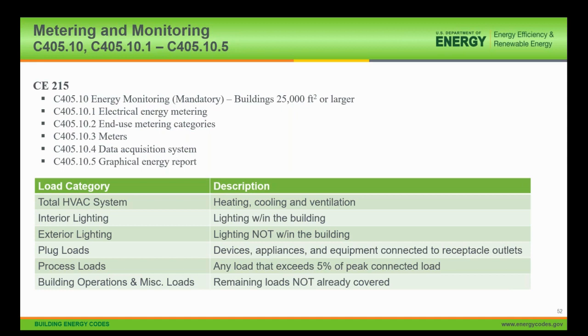So your mechanical system is metered, interior lighting needs to be metered, and your exterior lighting needs to be metered separately. Plug loads and process loads are separated, and process loads are defined as really anything that's 5% of your peak connected load. And then finally, there's building operations and miscellaneous loads.